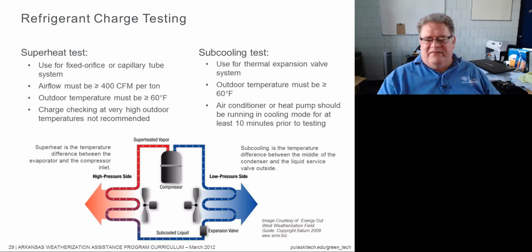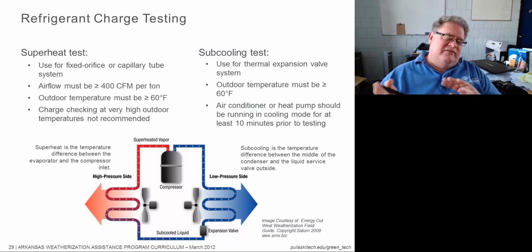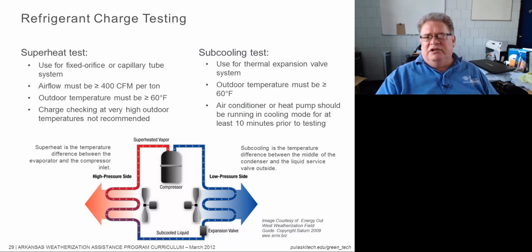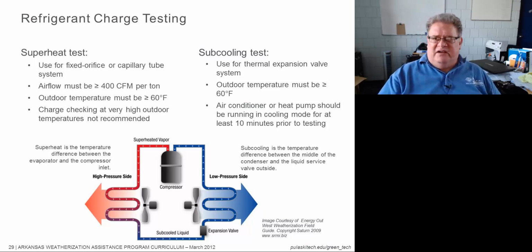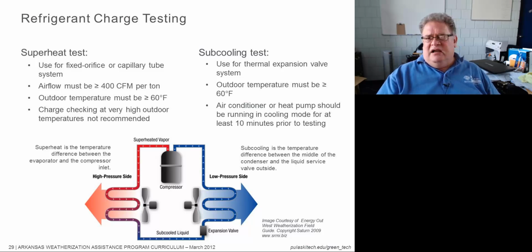I can't even remember what the name of the valve is. It's right down here, the expansion valve. Whether you have a thermostatic expansion valve, a capillary tube, or a fixed orifice expansion valve, okay? For subcooling, use it for a thermal expansion valve system, all right? Outdoor temperature has to be equal to or greater than 60 degrees. You can't test it too much lower than that.